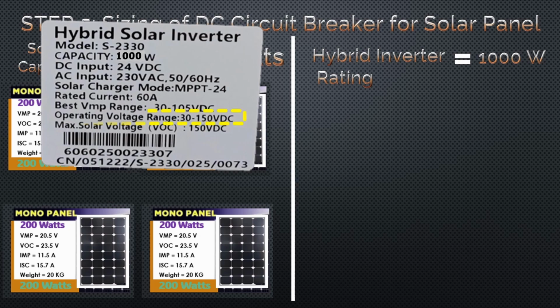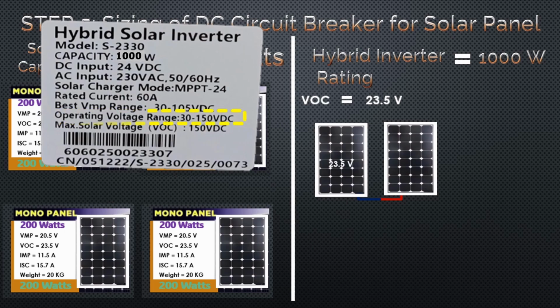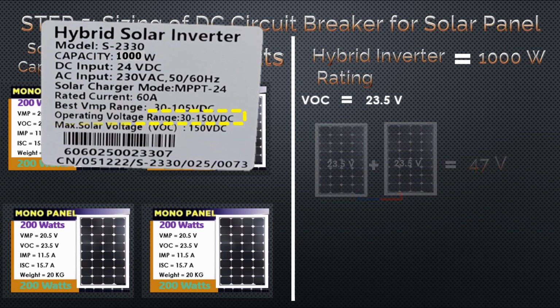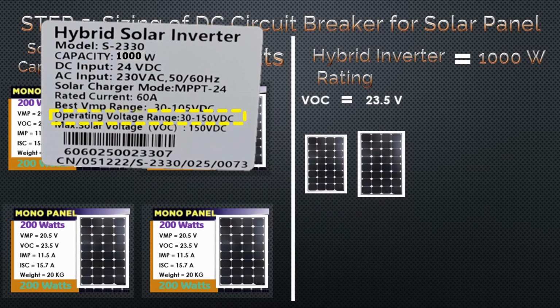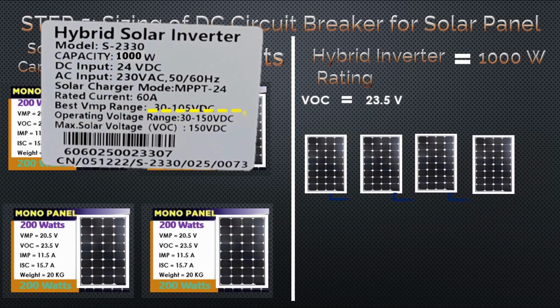Now find the VOC or open circuit voltage of the 200 watt solar panel that you will use. And based on the nameplate, the solar panel has a VOC equal to 23.5 volts. So based on the VOC of the solar panel and the DC voltage range of the inverter, you have two options regarding the possible connection of the solar panels. Now if you will connect two panels in series, you will add the VOC of two panels, and that is 47 volts. So it is within the range of 30 to 150 volts. Now if you will connect 4 200 watt panels in series, you will get 94 volts.